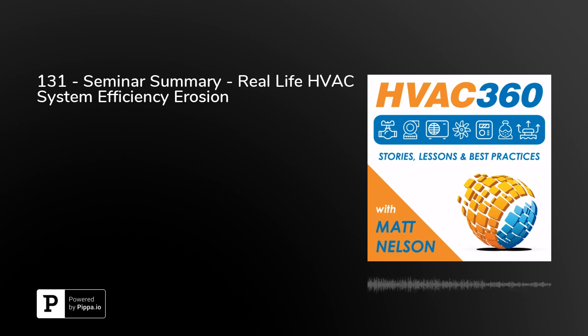Now, let me just state this from the session: homes are typically below 60%. So they're performing well below their rated capacity. Code compliance systems on the commercial side would perform in the low 60s. That was generally what they're seeing. This test really doesn't take too long, anywhere from 45 minutes to 90 minutes, depending on the size of it, with the commercial installations obviously taking a longer look at their systems. Generally speaking, the accuracy of what they're doing here is plus or minus 13%. So that is some of the data.